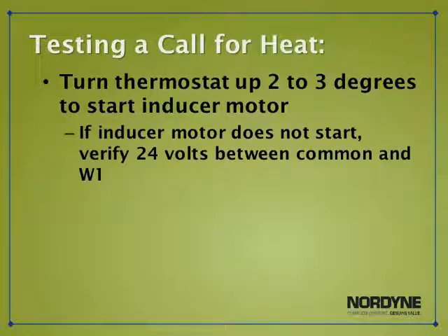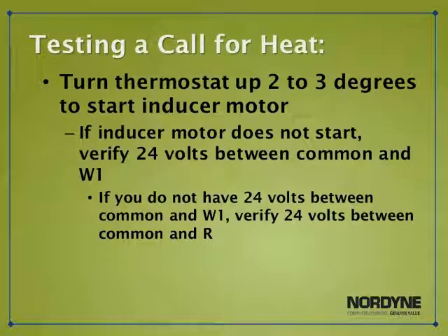If your inducer motor is not starting, we need to verify if you have 24 volts at your terminal strip on your control board between the common terminal and the W terminal. If you do not have 24 volts between common and W, we need to verify 24 volts between the common terminal and the R terminal.